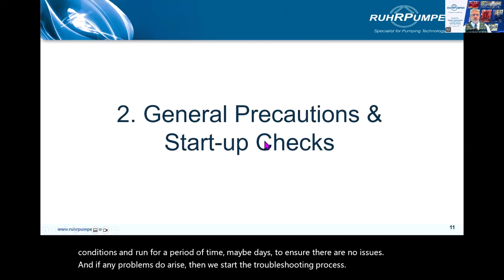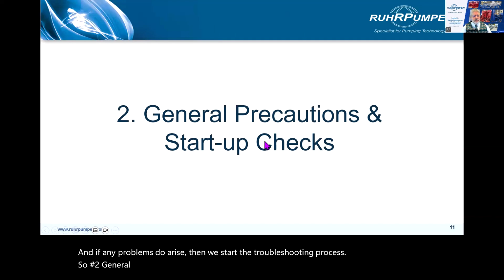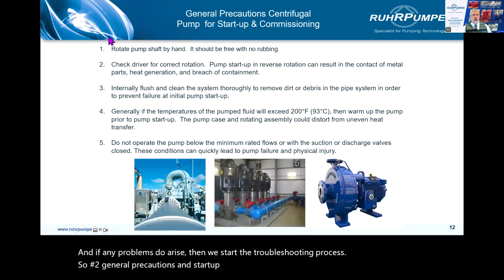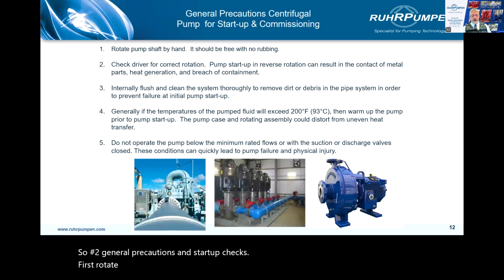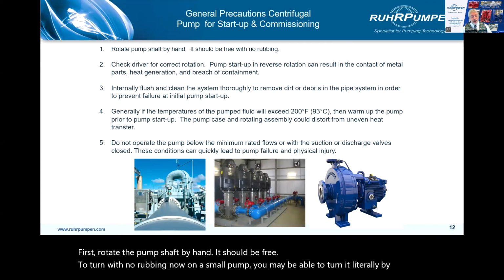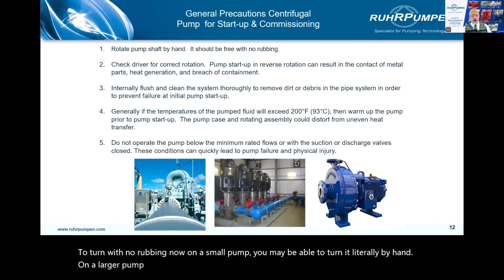So, number 2, general precautions and startup checks. First, rotate the pump shaft by hand. It should be free to turn with no rubbing. Now, on a small pump, you may be able to turn it literally by hand. On a larger pump, you may need to use a pipe wrench on the coupling spacer.